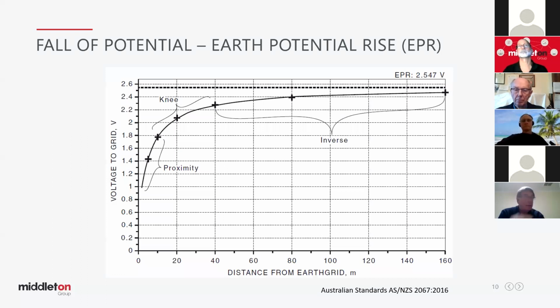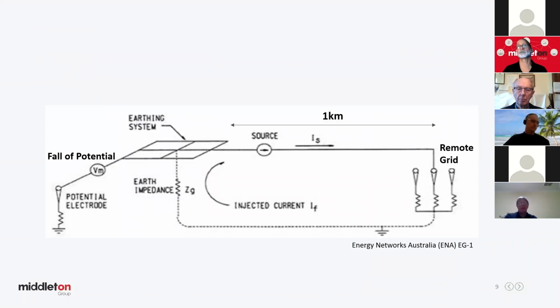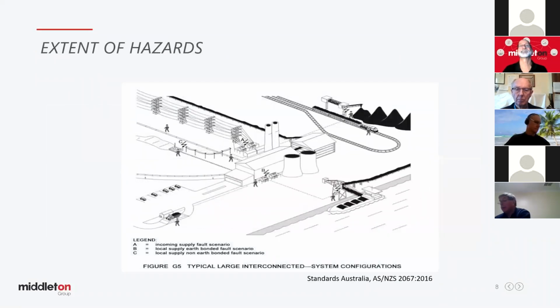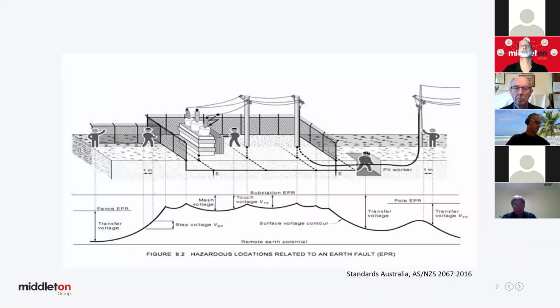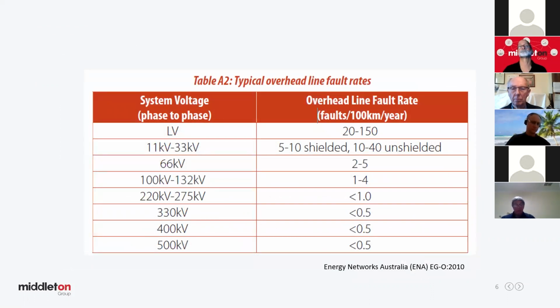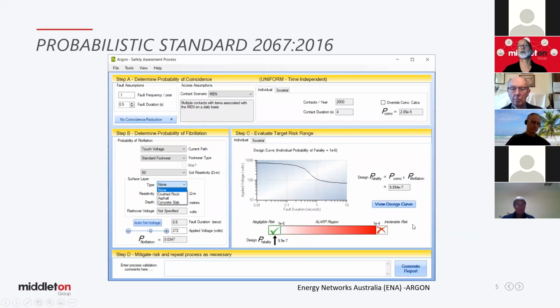software there, if I go back to it. Excuse me while I scroll back to it, try not to go past it and have to come backwards and forwards. It's further back than I thought. But in this Argon software, you'll notice, it's the next page, that we have risk down here. So the client or the utility may even consider accepting a risk above 1 times 10 to the minus 6. They consider accepting as low as reasonably practicable for a year or two, where they then know that the planning department is going to have an MEN encroach from the main MEN around this, and then it can be common bonded.